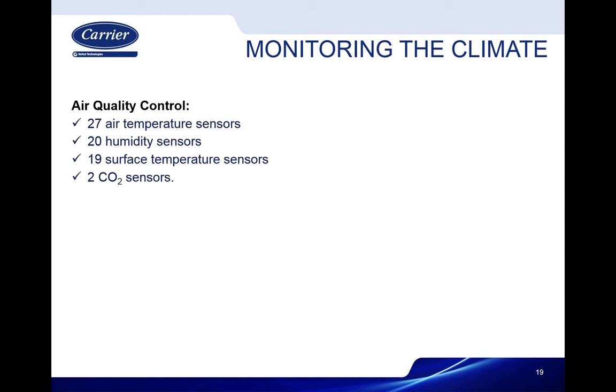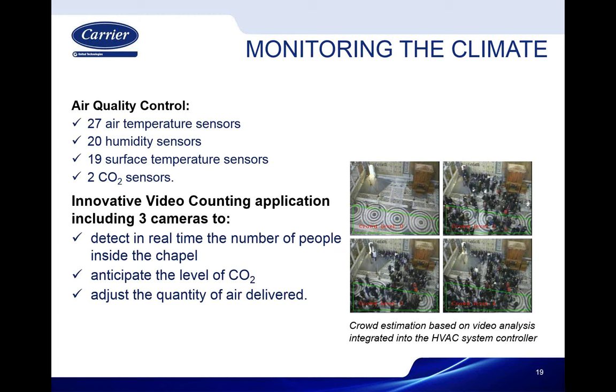I didn't mention earlier, we were actually doing dew point sensing. The primary set point of this system is to maintain a dew point depression of at least 10 degrees C below the surface temperature of the fresco wall where the painting is actually done. So anytime the wall temperature changes because of what's happening outside, there's a 2 to 3 day lag. Let's say you had a heat spike and 2-3 warm days, it'll be up to 3 days before the wall on the inside even feels and registers that.